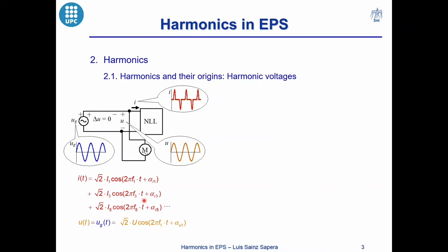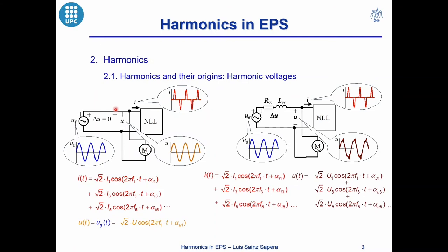In conclusion, even if there are nonlinear loads in the circuit, there will be no harmonic voltages when the grid has no impedance. On the other hand, the voltages become distorted and contain harmonics when there are nonlinear loads injecting harmonic currents through the impedances of the grid. We can conclude that the origin of harmonic voltages is the presence of harmonic currents injected by nonlinear loads and the impedance of the grid.